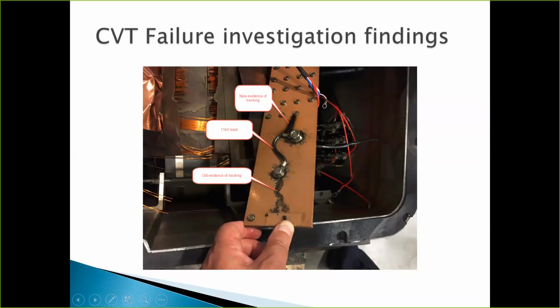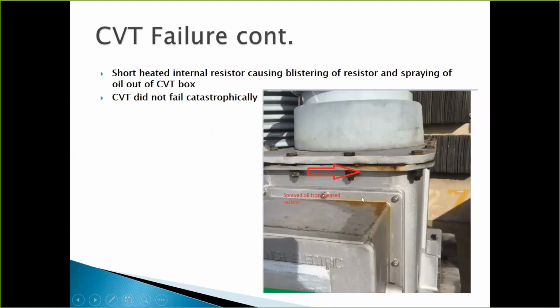The carbon path was relatively new. Okay, so what we found was in the tank that heated when it saw that short. There's a resistor in there that's part of the ferroresonance network. It blistered and it sprayed oil out of the corner right here. Okay, the short heated it. It caused blistering, and then it sprayed a little bit of oil out on the tank.